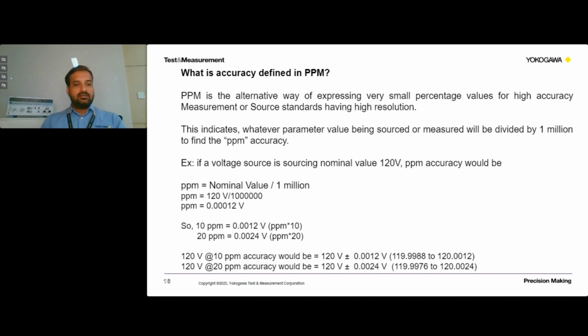Further, when we define a source of 120 volts with 10 parts per million accuracy, we are saying that it is 120 volts plus or minus 0.0012 volts, and the range of values we get when we do the measurement will be from 119.9988 volts to 120.0012 volts. So this is an example of how parts per million accuracy is calculated.